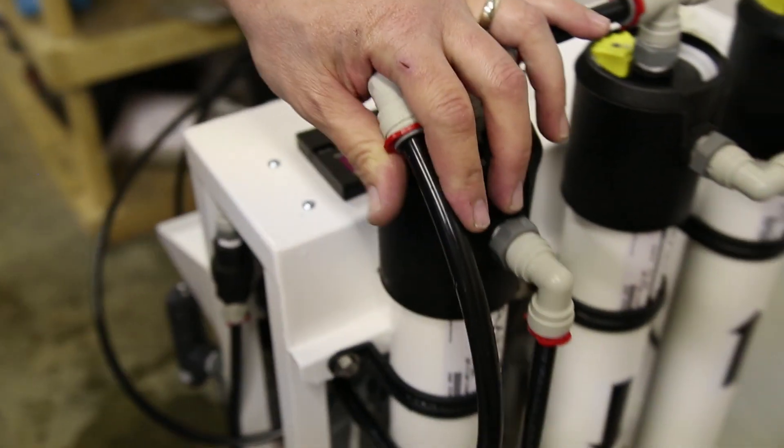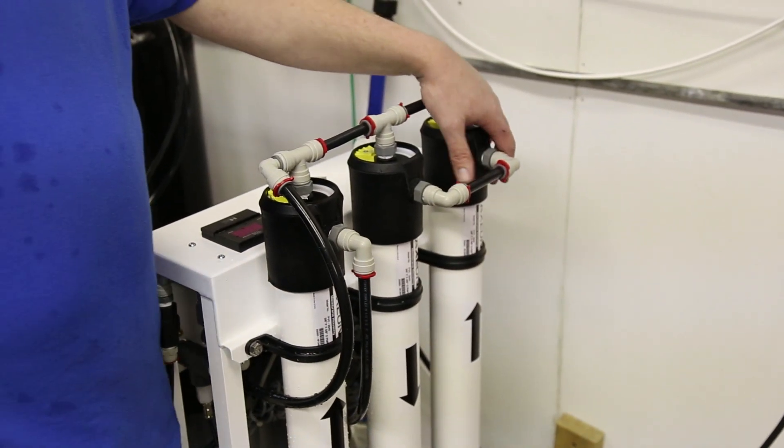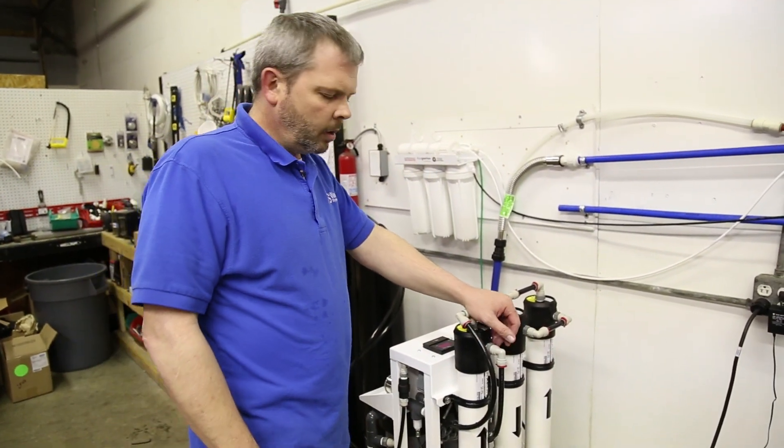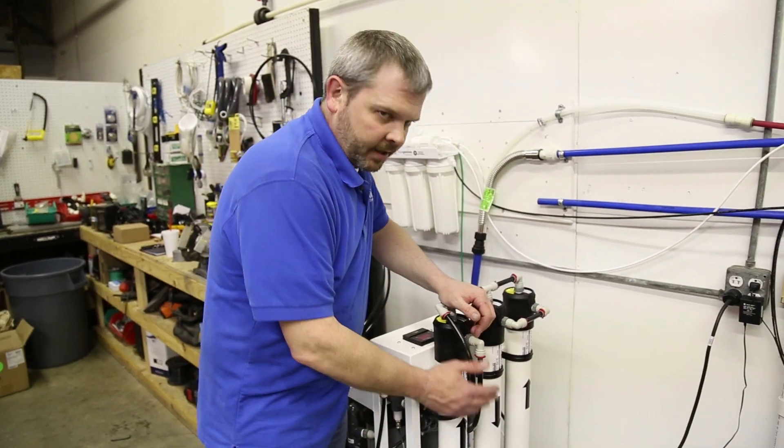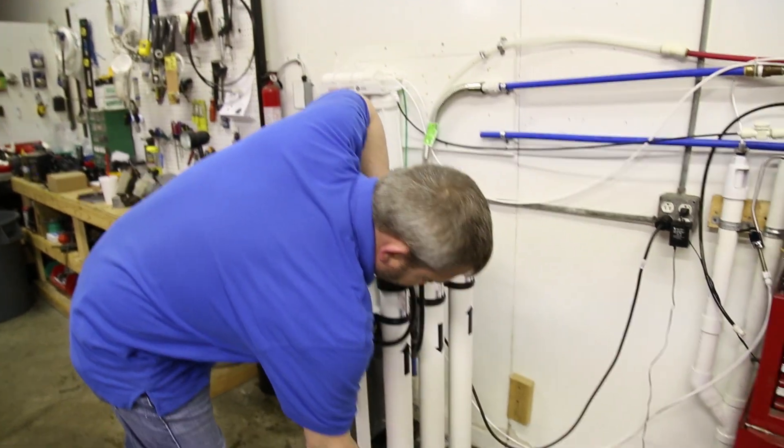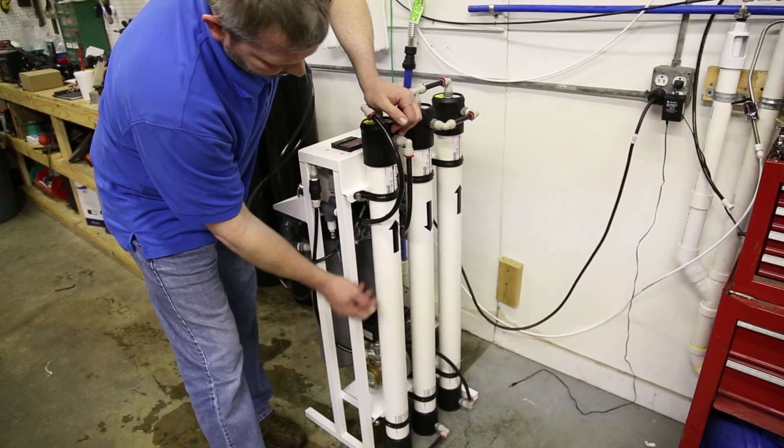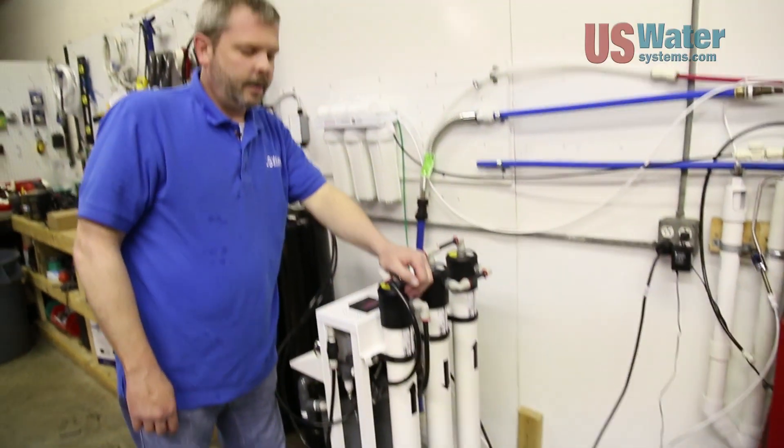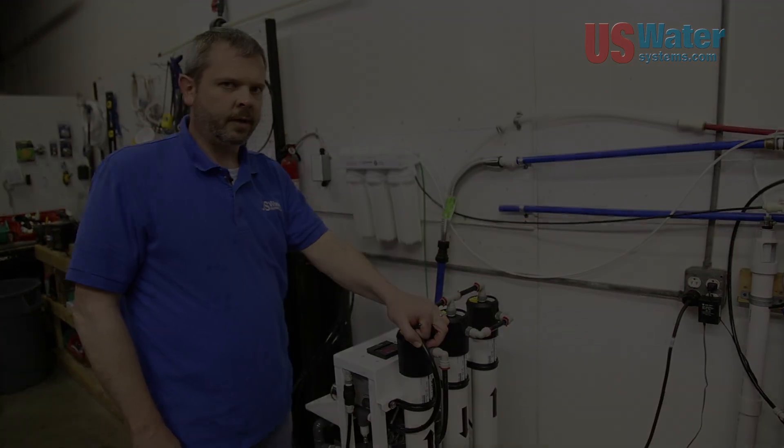Now once this is done, you basically would repeat that for each membrane. Then you'll go through the complete start-up process again. You're going to treat this as a new install and go completely through the start-up process. But keep in mind, there's a proper way to put the membranes in. The skirt seal should always be on the feed side of the membrane housing. This is the commercial membrane change for US Water Systems, thanks.